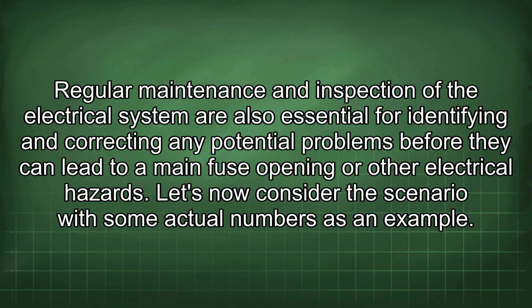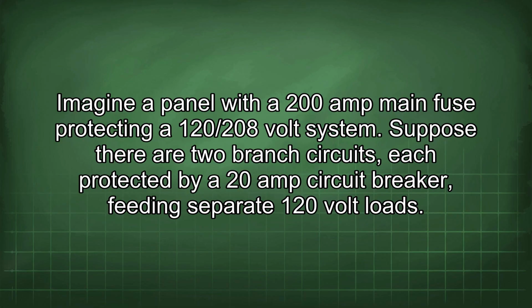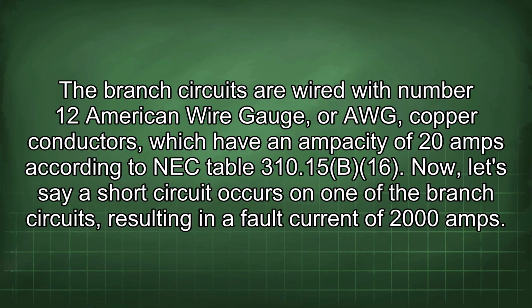Let's now consider the scenario with some actual numbers as an example. Imagine a panel with a 200 amp main fuse protecting a 120/208 volt system. Suppose there are two branch circuits, each protected by a 20 amp circuit breaker, feeding separate 120 volt loads. The branch circuits are wired with number 12 American Wire Gauge, or AWG, copper conductors, which have an ampacity of 20 amps according to NEC table 310.15(B)(16).